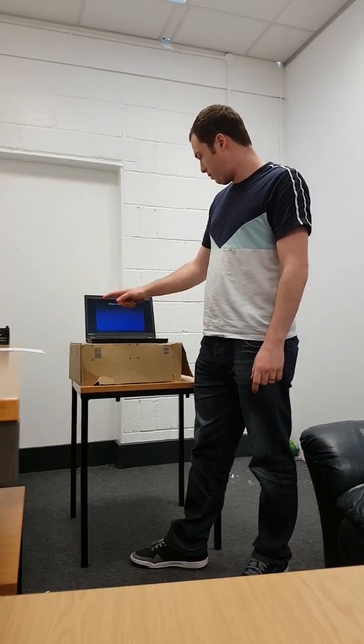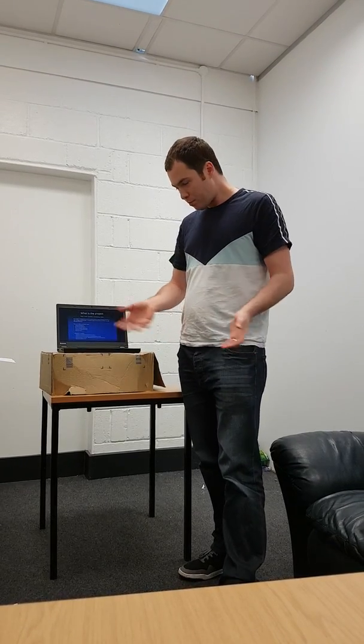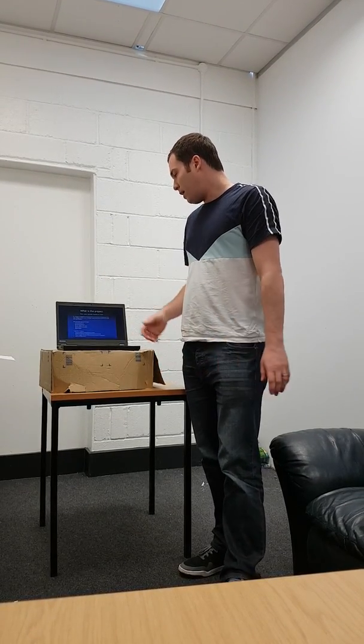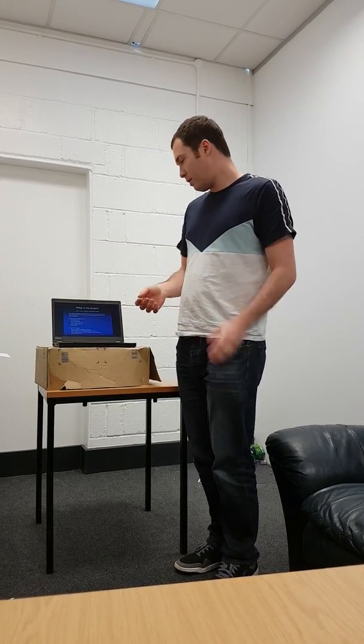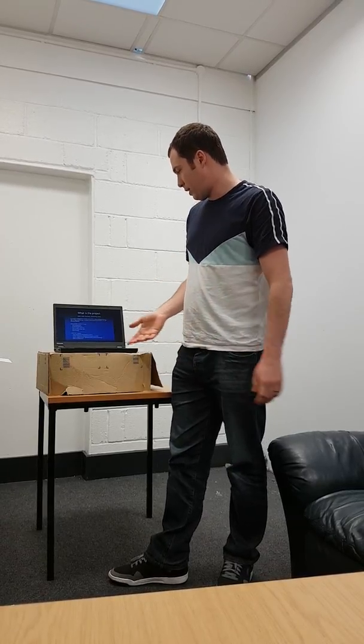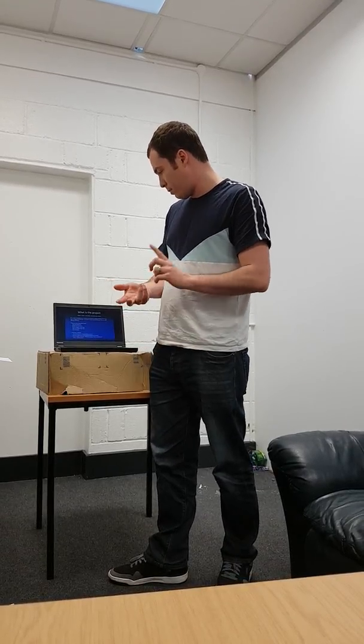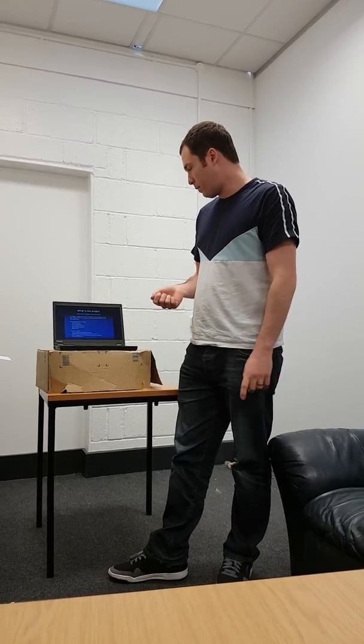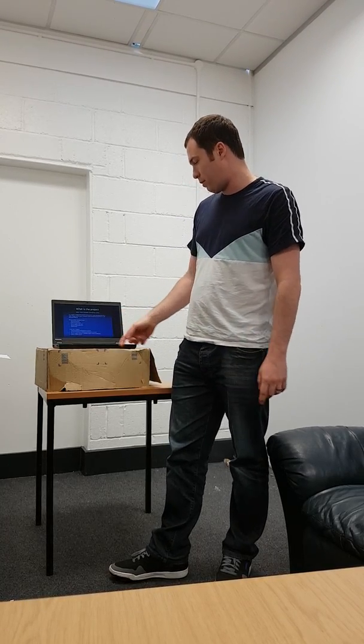My project comes in here. These power supplies sometimes fail when you test them, so we take them out of service and test them separately, and we have to put a resistive load into this because we have to mimic the load. So my controller controls the water-cooled load and all the dedicated interlocks for it. For example, the inputs: it has to handle water temperature, inlet temperature, outlet temperature, power supply flow, resistor flow, and a reset button when it locks out, and vice versa for the outputs.